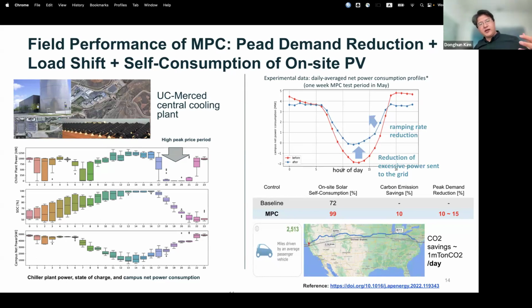So we developed and tested the MPC with the plant, testing two different things. One is we injected a typical dynamic utility price signal to the building and observed the savings, particularly dollar savings associated with the MPC. The other is we took a carbon price signal from the grid.